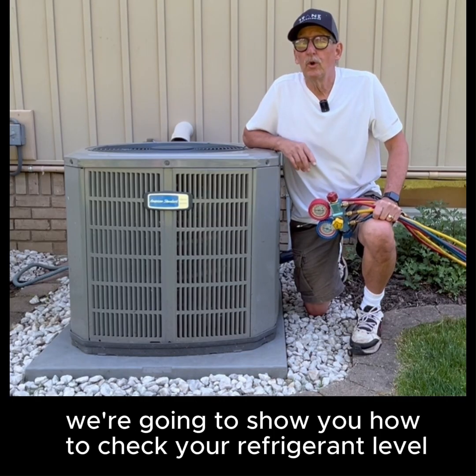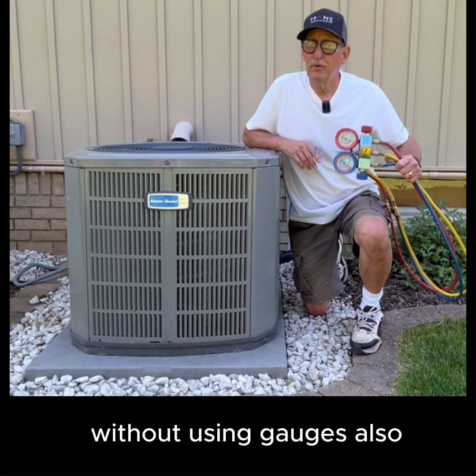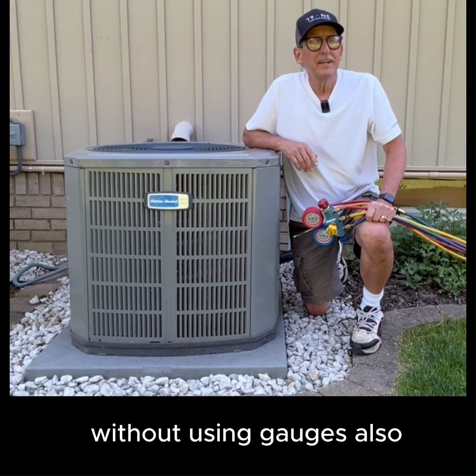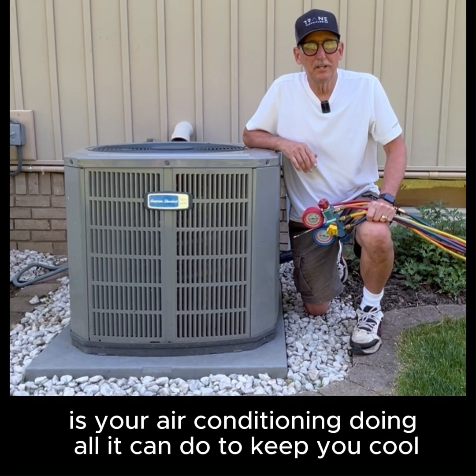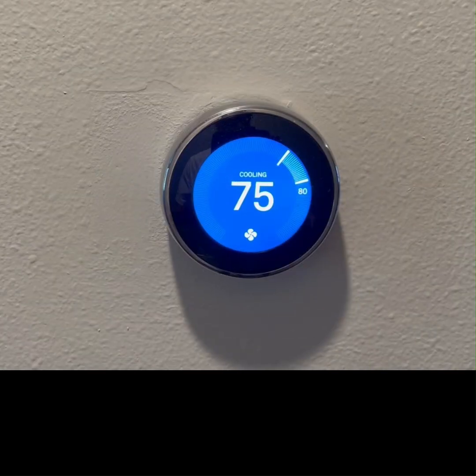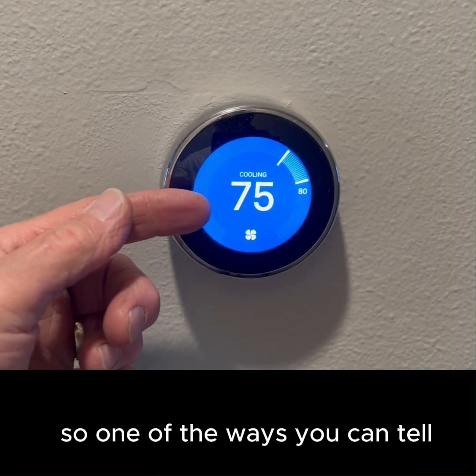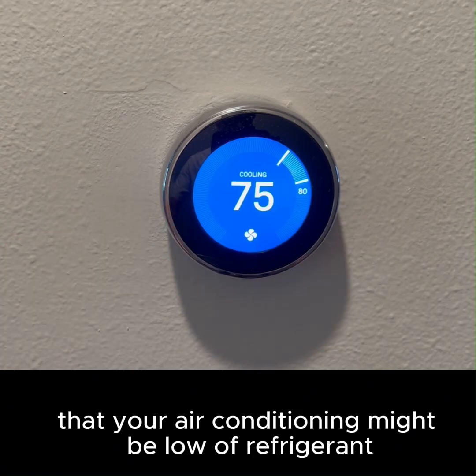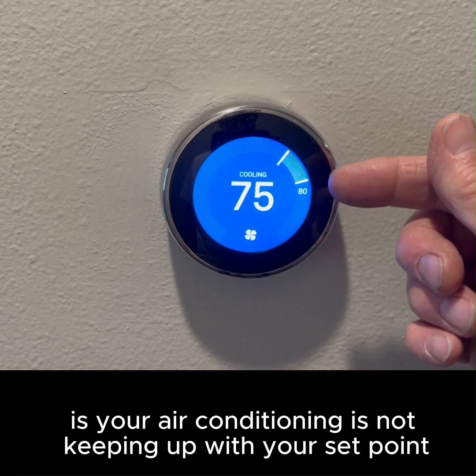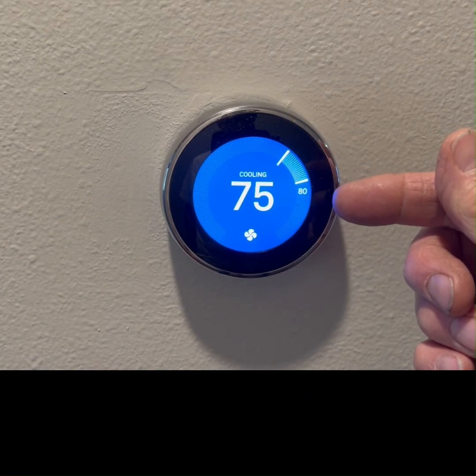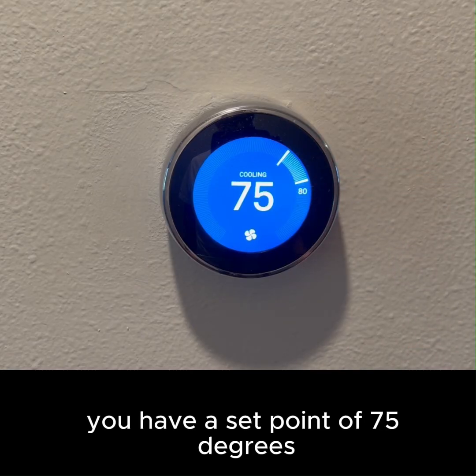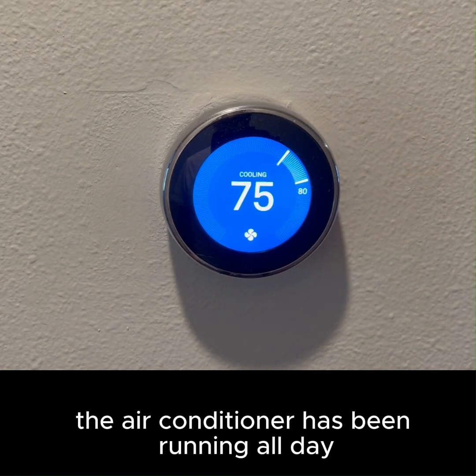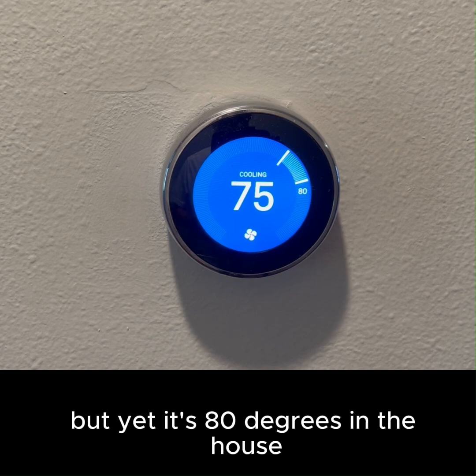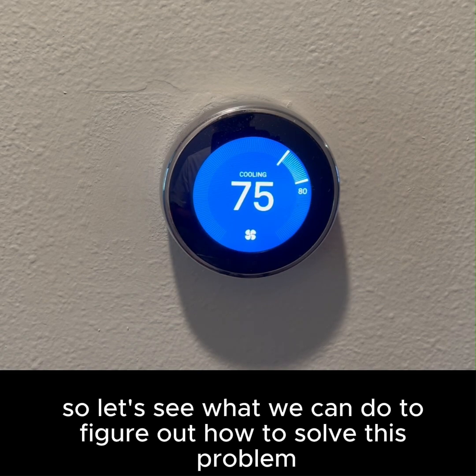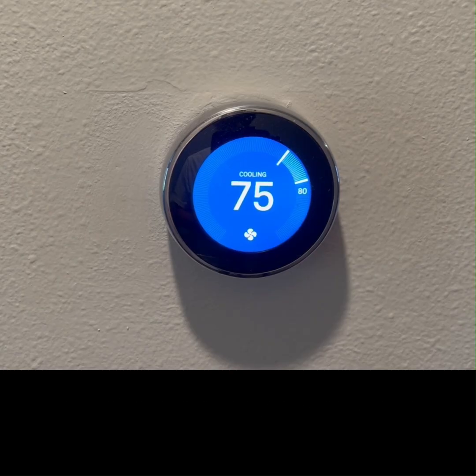Today we're going to show you how to check your refrigerant level without using gauges. Also, is your air conditioning doing all it can do to keep you cool? One of the ways you can tell that your air conditioning might be low on refrigerant is that it is not keeping up with your set point. You have a set point of 75 degrees. The air conditioner has been running all day, but yet it's 80 degrees in the house. So let's see what we can do to figure out how to solve this problem.